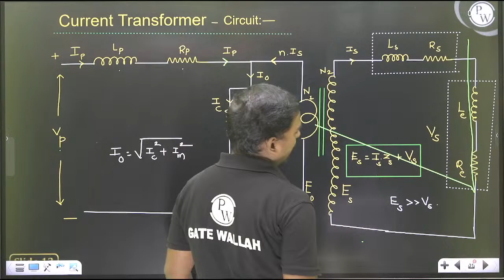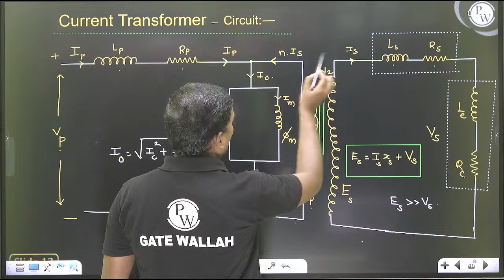The most important point to understand here is the components. This is the primary side component IP, primary current, which is split into two parts: one is I0, called the no-load component, and the other is N into Is. The secondary side current is Is, and this represents the reflected current of the secondary at the primary side.